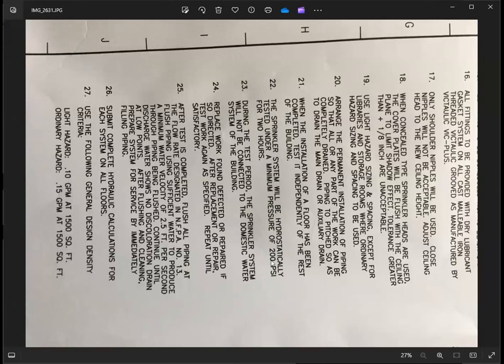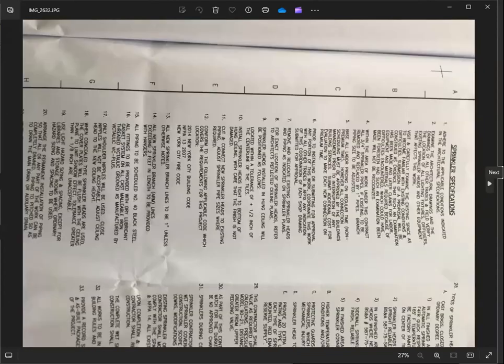So I used to tell the guys, the installer, to make it more than 200. So just in case it drops a little, I could only adjust the time of my test and not the pressure, not necessary to pump it up again. So that's the adjustment that I usually do during a hydro test for sprinkler systems or standpipe systems.